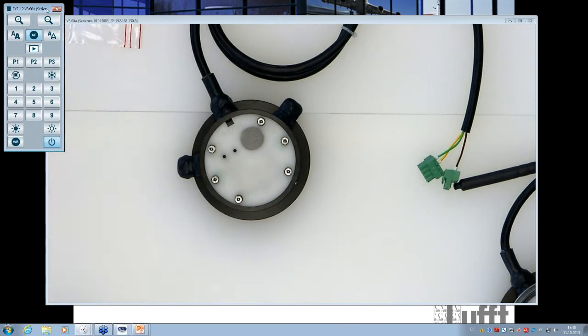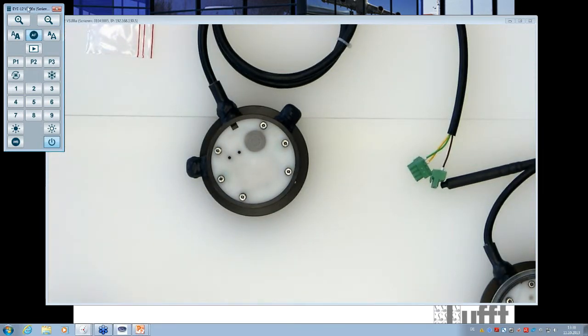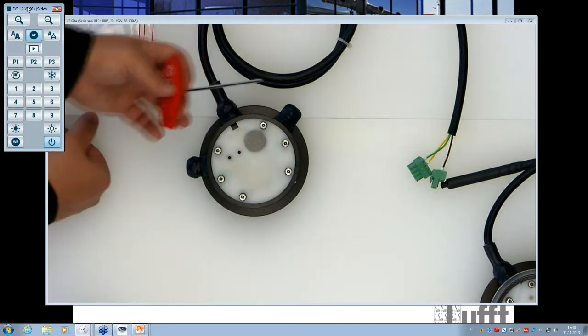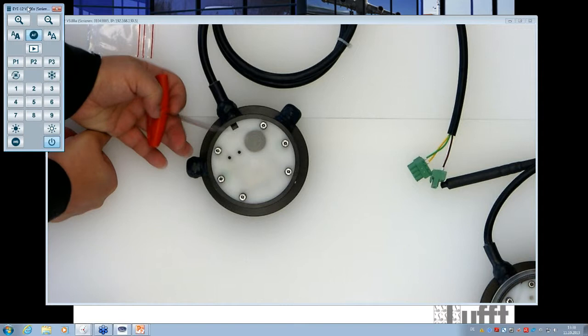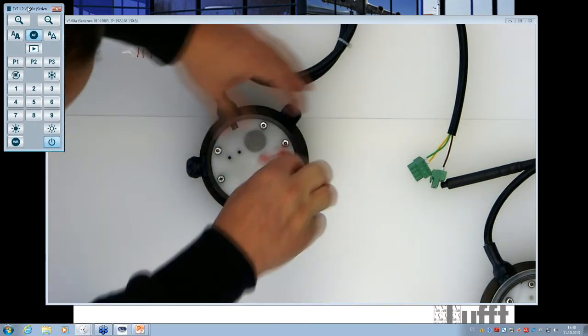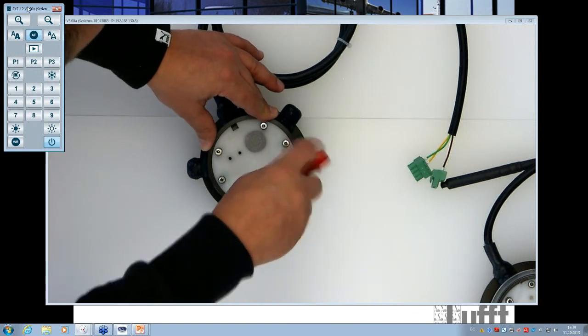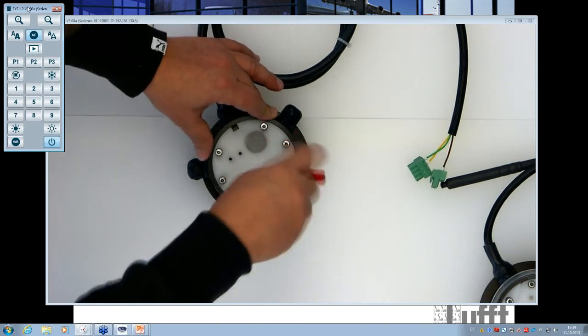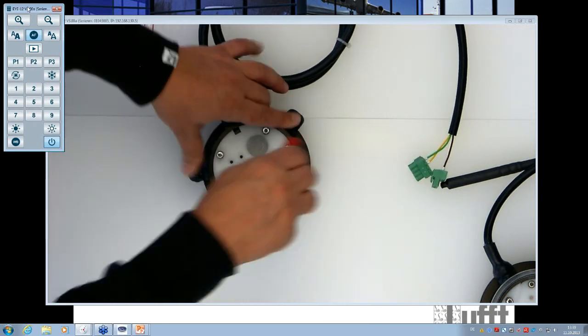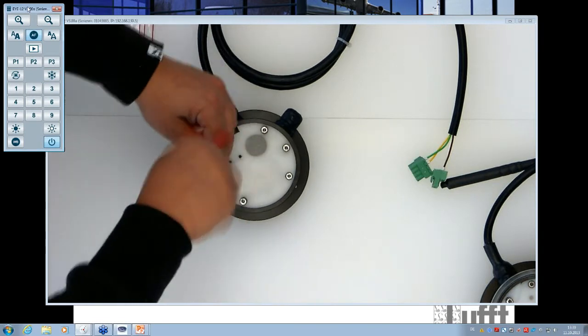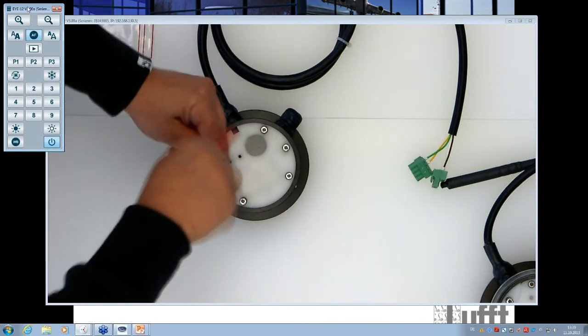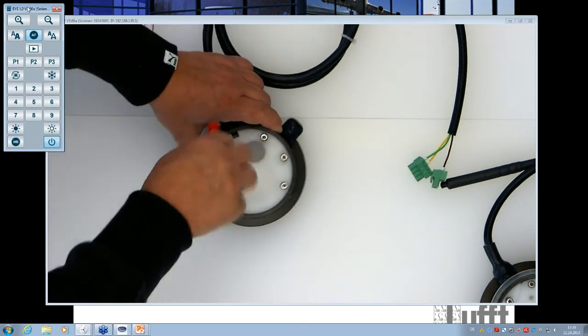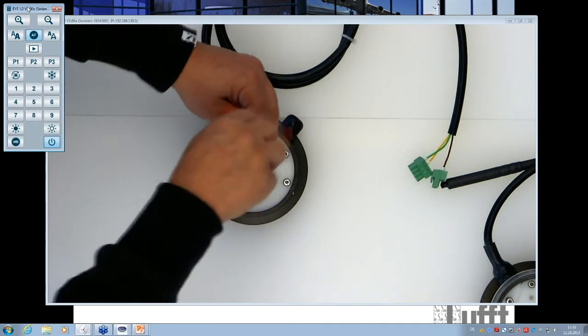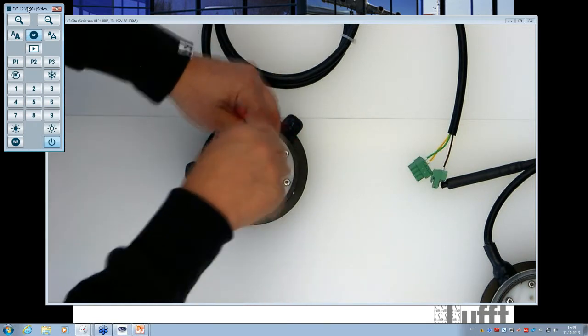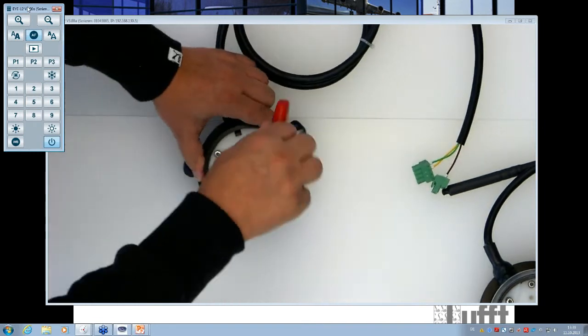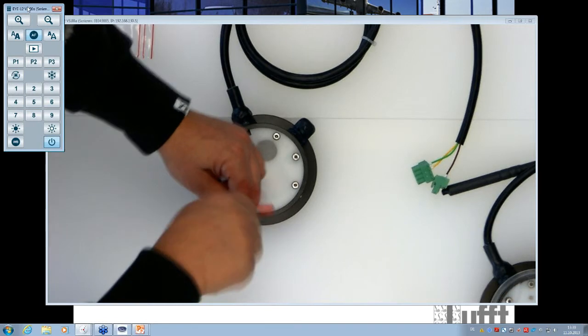And now you have to use this special wrench, this hex wrench with a torque of 2 Newton meters. So to use the right power for the sealing. I will do it without this special wrench because I do not have it here. But normally here, if you are in front of the station, you have to use it with 2 Newton meters. And after this procedure, the electronic part is changed. And I think it's an easy thing to do. The most important thing is to use this new sealing. That's really important. If you do not do it, you will get problems with water which will go inside the housing here.